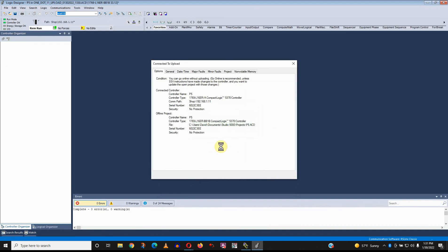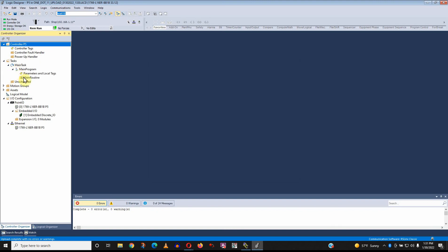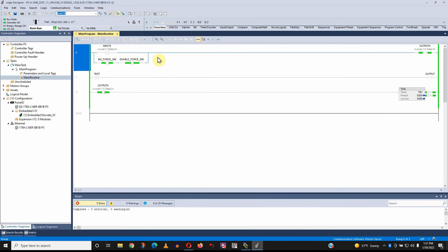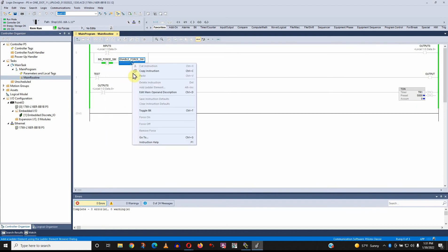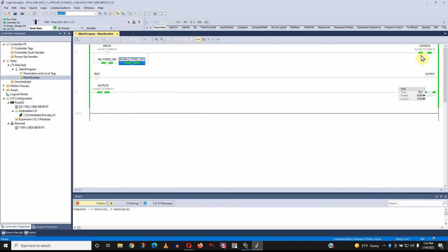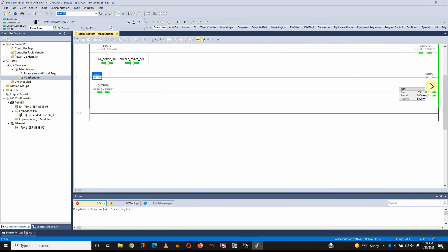It's uploading across the ethernet right now, so it takes a second. Keep in mind that if you ever have to, you can plug a USB cord into the front of the processor and do an upload across it if for some reason you can't get online with it. Here is the program that's running in the processor — it's a really short program I wrote just to demonstrate toggling of bits. Toggling works when you have base tags like these. This is an alias tag — alias tags connect to the outside world. I can toggle base tags on, turning on a real output, because this is an alias tag for output one. Here are a base contact tag and a base coil tag.